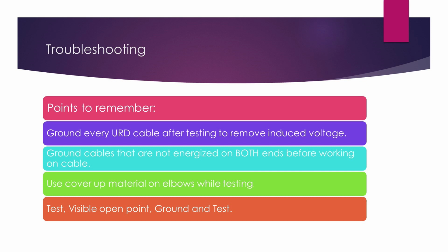What happens is this underground wire is built so well and constructed in such a manner, with the concentric around the primary and all the insulation involved, that when you put 7.2 or 7.6 or 14 kV through that wire, then pull that elbow back off and put it on a parking stand, it can retain that voltage. It can hold on to 5,000 volts, 500 volts, 100 volts, or 1,000 volts—just like a battery, just like a capacitor. Unless you ground this, it's just going to sit there and wait till somebody makes a mistake and gets bit. So make sure you ground it, for that reason alone, to get that induced voltage and capacitance out of that wire.